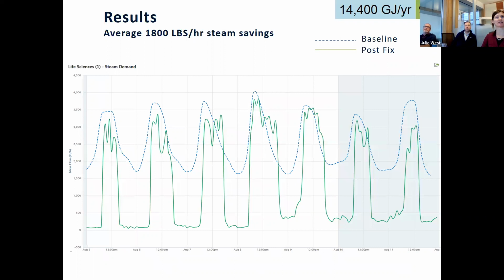So looking at the results of that, the baseline energy use is the dotted line here, what it was doing before, and then post-fix is the line afterwards. So you can see that during the nighttime or daytime, I'm not sure which that is, it's actually recovering a lot of heat. And this saved roughly 15,000 gigajoules per year, almost 10% of the building's energy use, just by getting that heat exchanger working.